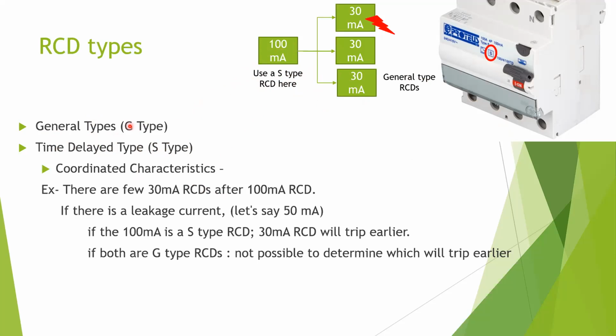S means slow type. So this is general type, slow type. The slow type will take some time to trip. These are only for the purpose of what is called discrimination. In a case of fault, only the lower level of installations will be tripped without interrupting the other levels. That is the main purpose. We are also going to do a lab on discrimination, not on RCDs, so you will understand these discrimination studies in a few upcoming lectures. And that is the main thing you need to know about RCDs.